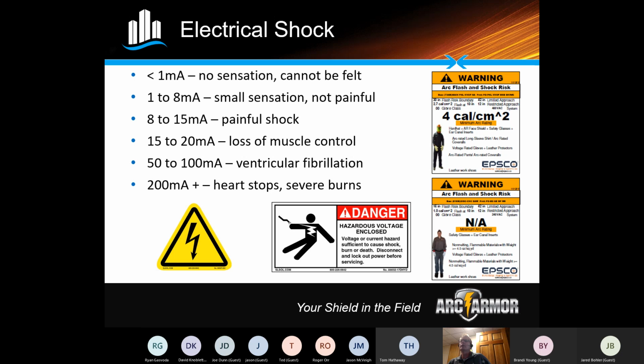This sticker right here shows you it's in calories per centimeter squared. And here it shows you need a hard hat, a face shield, safety glasses, and ear canal inserts. And then you should also have a long sleeve shirt that's arc flash rated, all those things. Most of the time in going into these types of panels, it's just good to know what's available to cause any issues. If you're talking 230 volt, 480 volt panels, which are pretty common on lift stations, having the proper PPE when you go into those is critical.